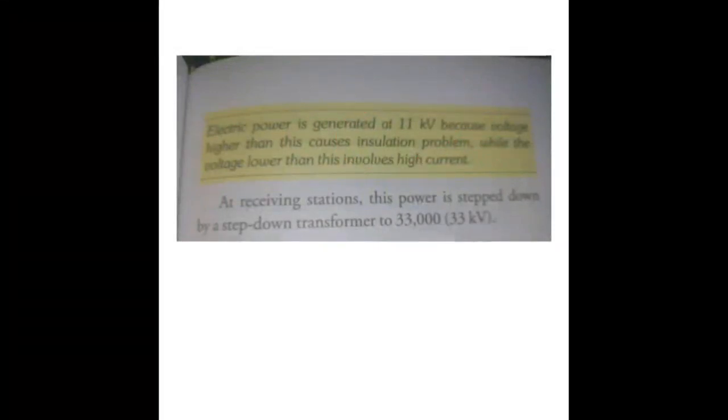Electric power is generated at 11 kilovolt. It is generated at 11 kilovolt because voltage higher than this can cause insulation problems, and lower than 11 kilovolt involves higher current which causes a heating effect. In the grid system, power generated at the power station is stepped up, and eventually it gets reduced until we consume it in our homes or city.